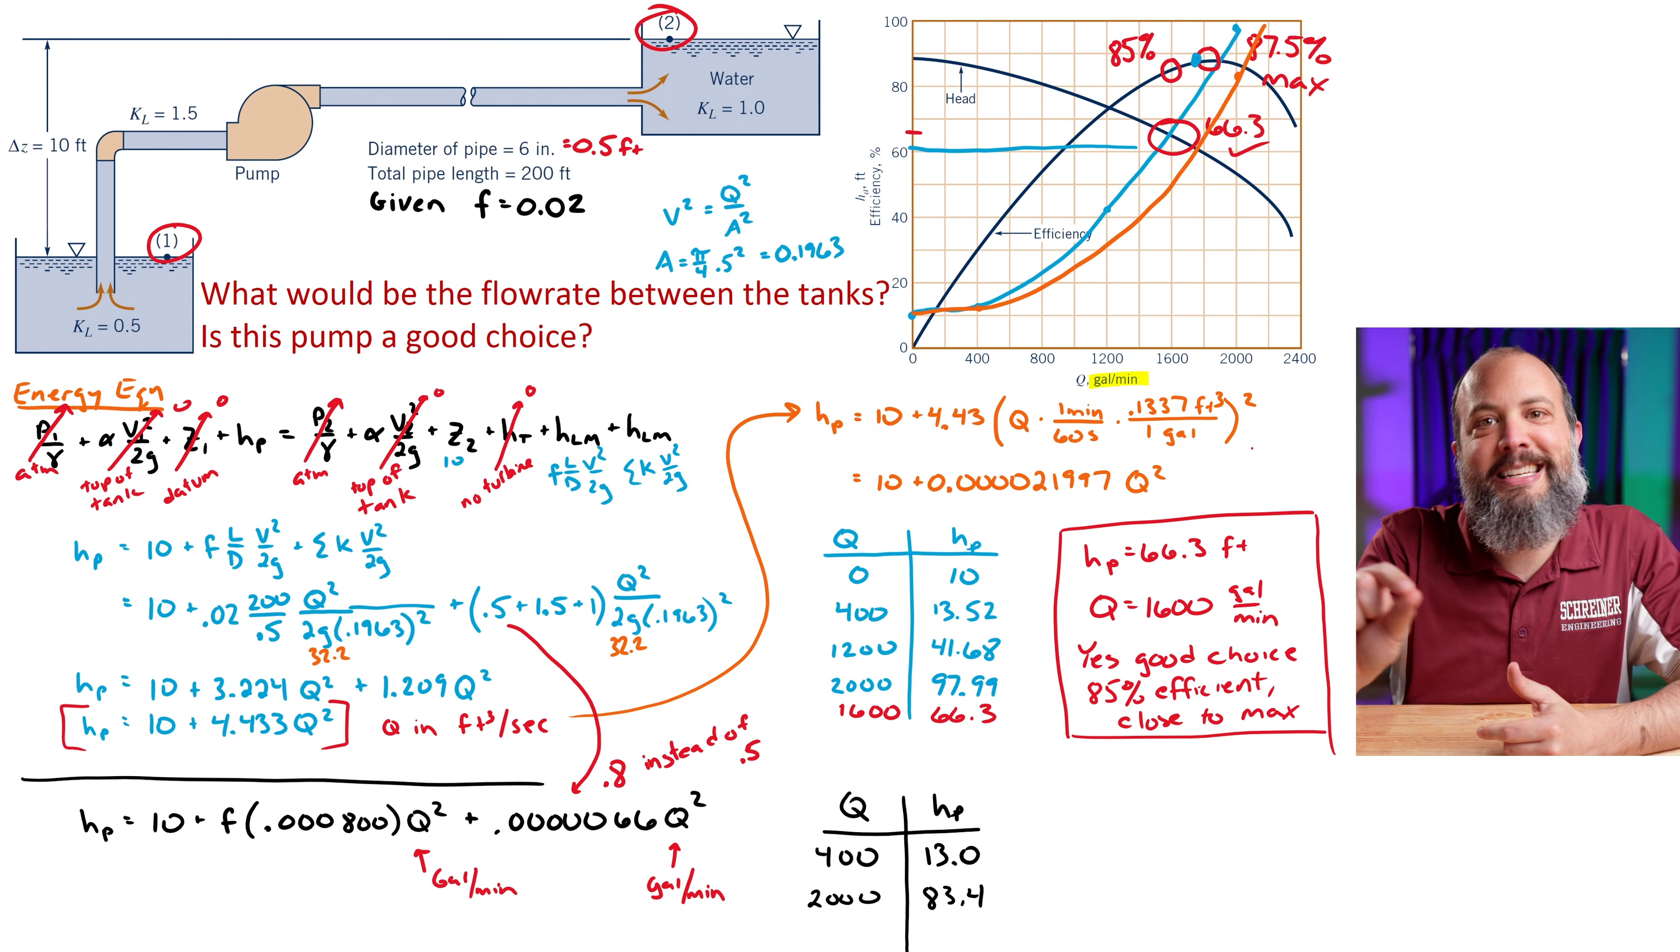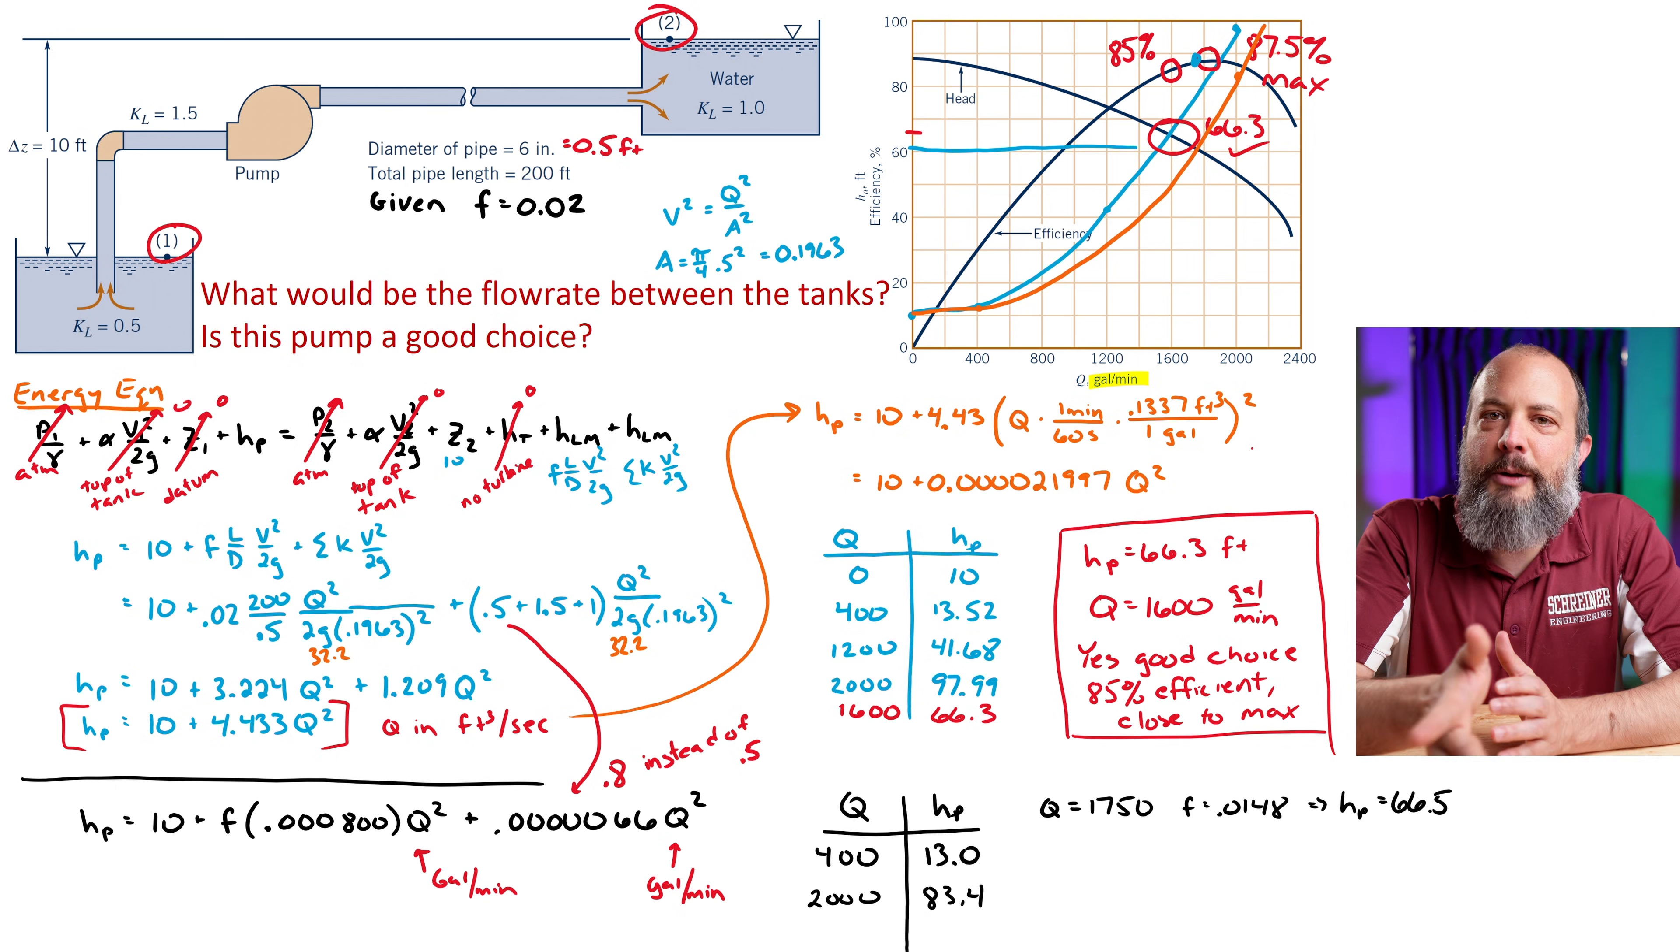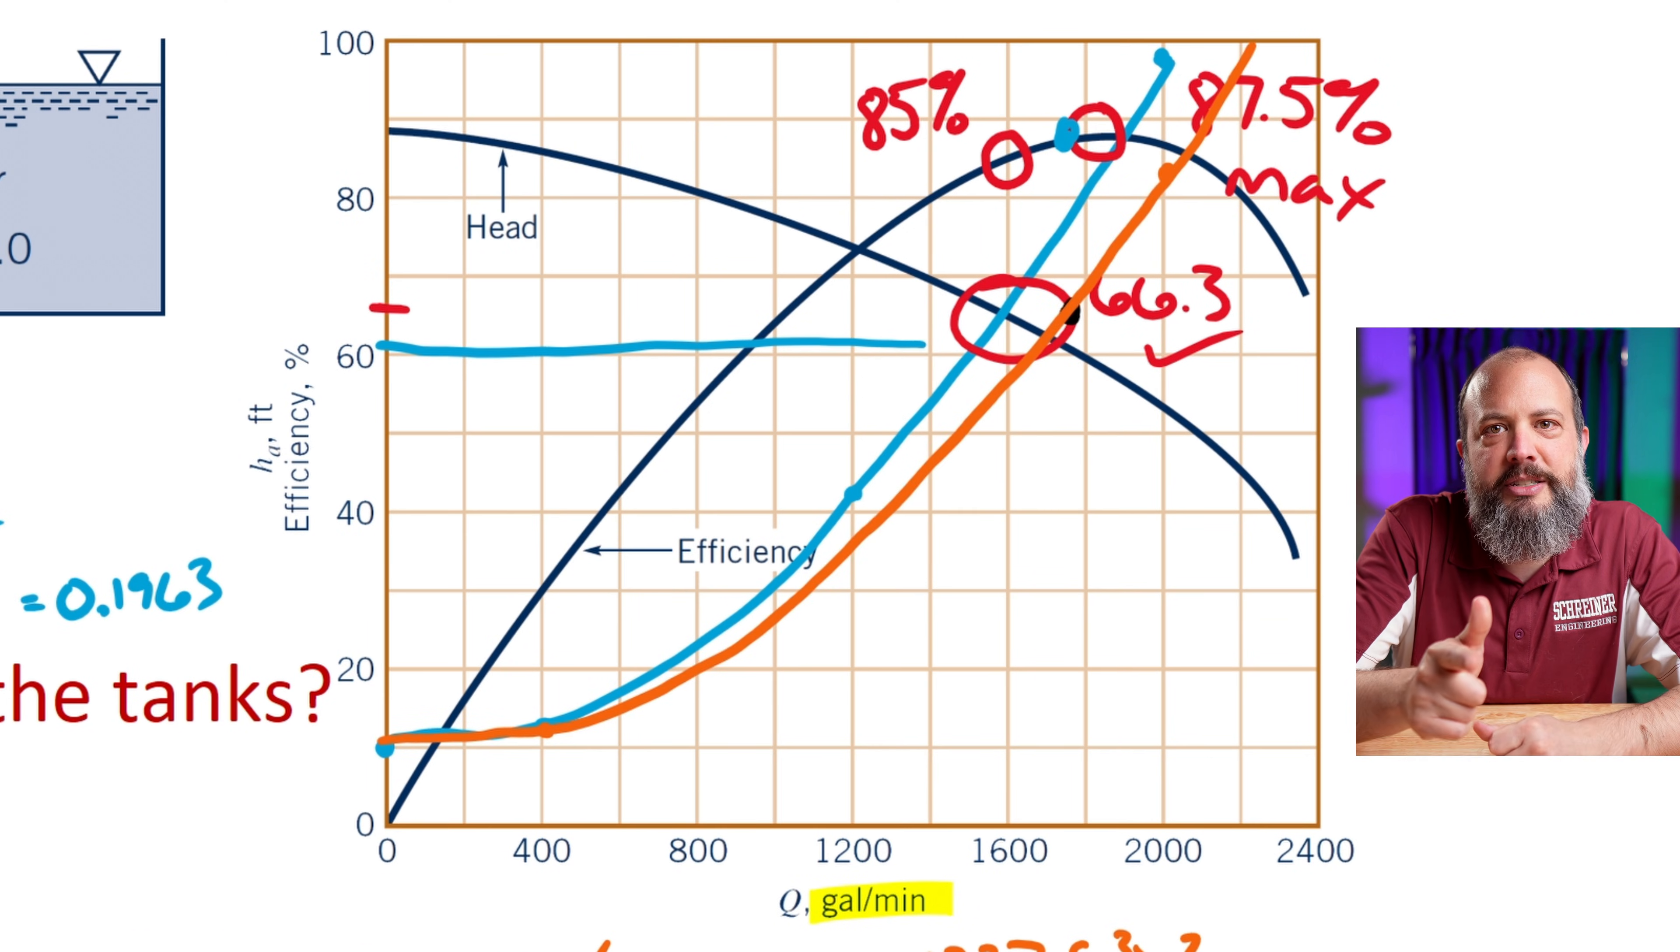So since 1750 is pretty close to the 2000, I'm not going to go calculate another Reynolds number. I'm just going to use 0.0148 as my friction coefficient, which is pretty close to the 2000 number, but in between the two. And I get a pump head of 66.5. Now, when I plot that on the drawing, that point is noticeably above the pump curve. So this means I need to redraw my line to be a little bit more accurate to be able to see a little bit better where the answer probably is.